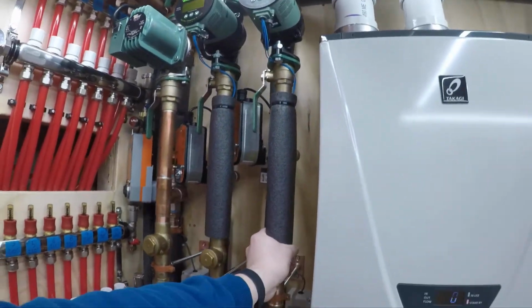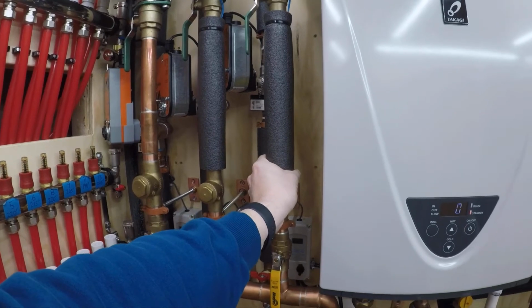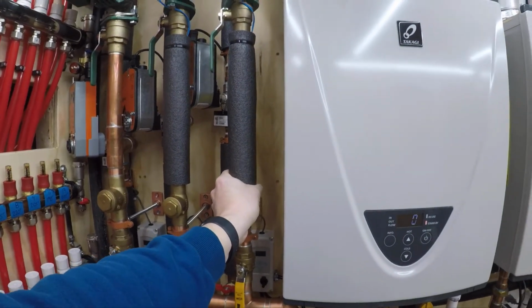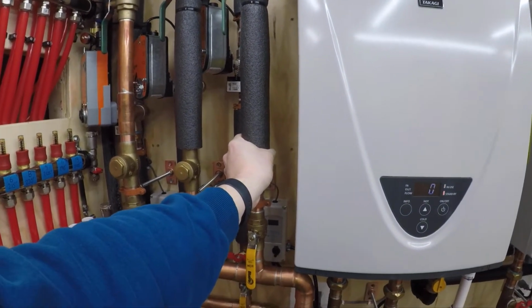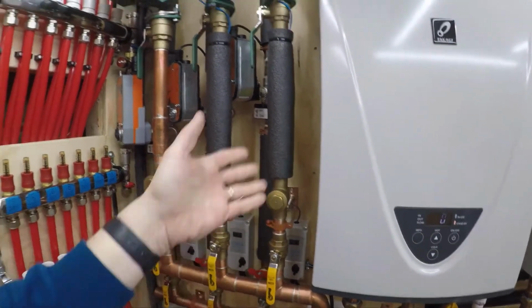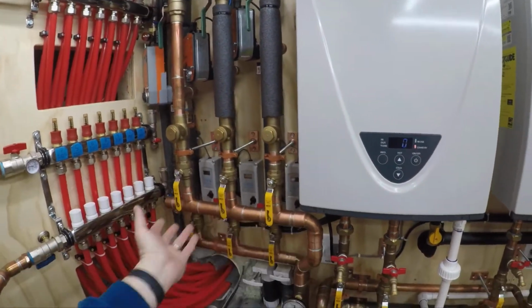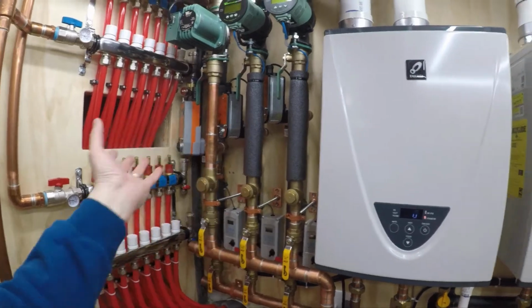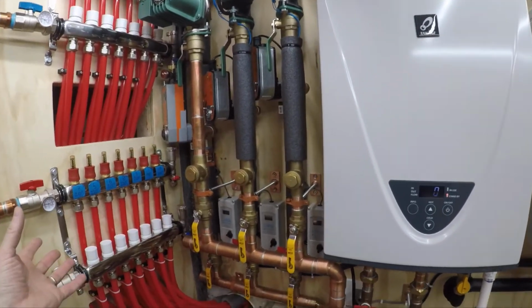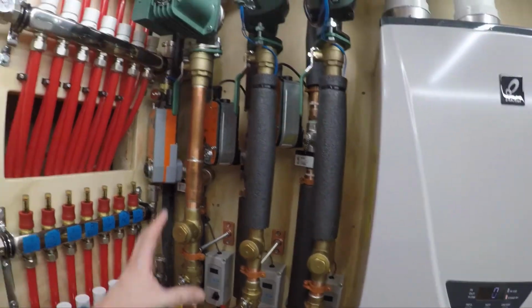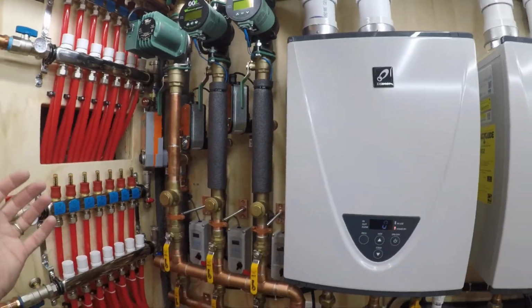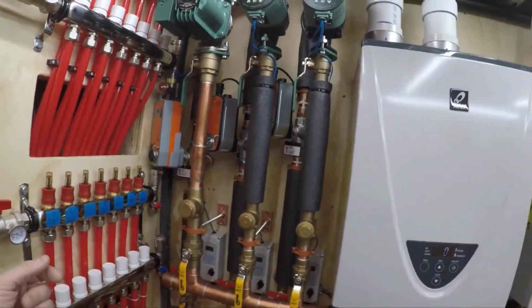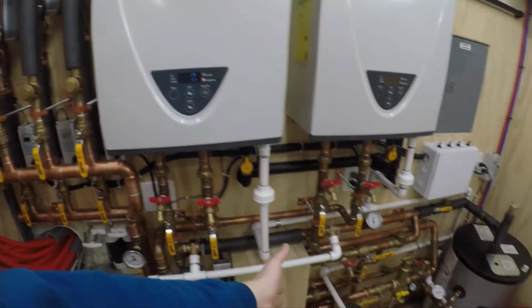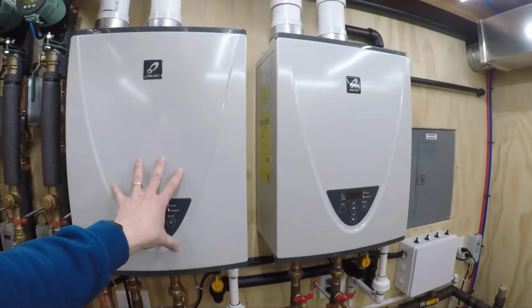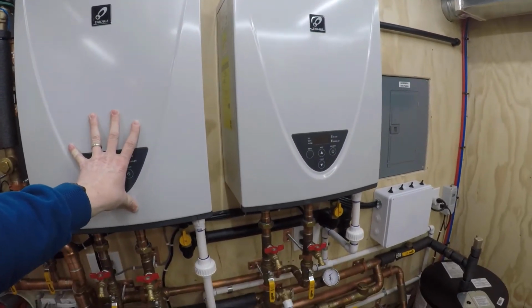So this first one right here is my staple up, and my staple up needs the hottest water first. Even though all three of these are really going to get the same temperature, it's not like there are mixing valves here, so they all get whatever they can get, which is usually about 100, and it depends on how many of them are drawing, but it's anywhere from 100 to 130 that the flat plate can steal from the primary loop side, which has 140 in it.